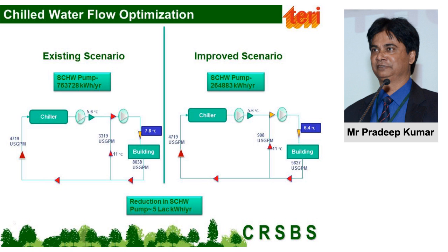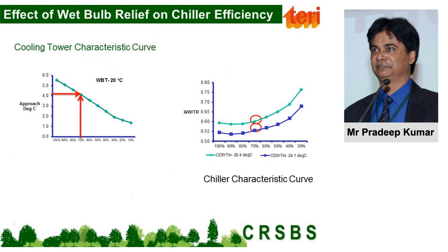Now this is something very interesting I'll share with you. The effect of wet bulb, or you can say the moisture content outside. Look at the cooling tower characteristics. This is also a weather dependent system. If my outside wet bulb temperature is 20 degree, and my chiller is loaded 70%, approach is somewhere around 4 degree. So the water which is leaving the cooling tower should be 20 plus 4, 24 degree.